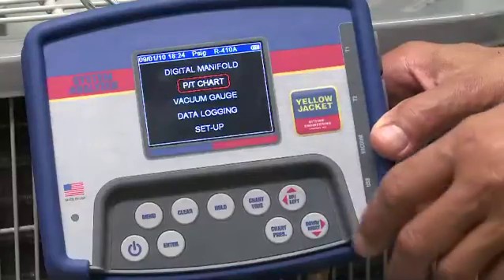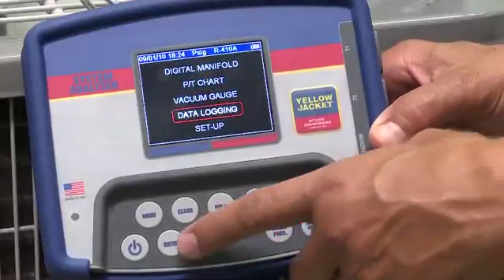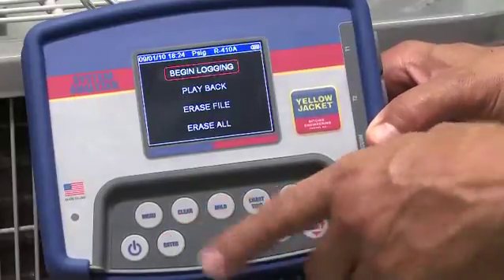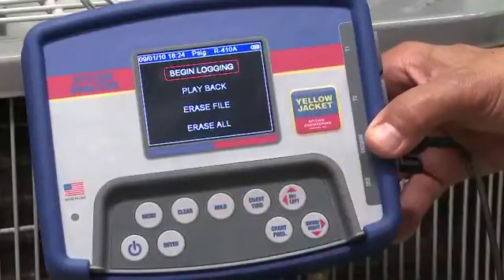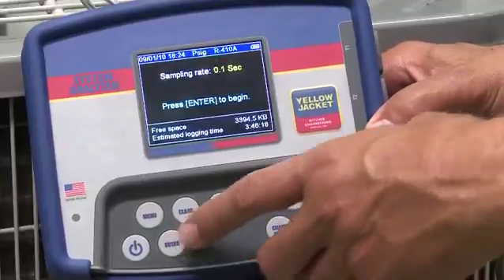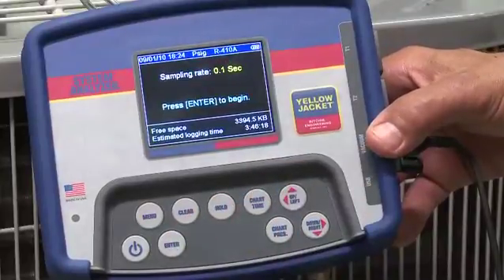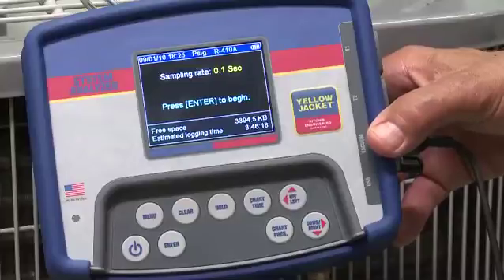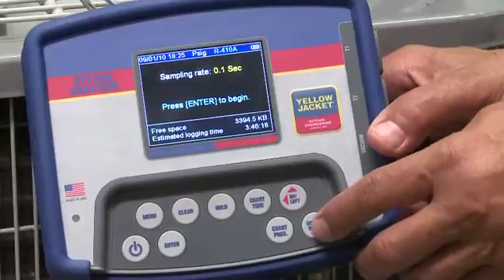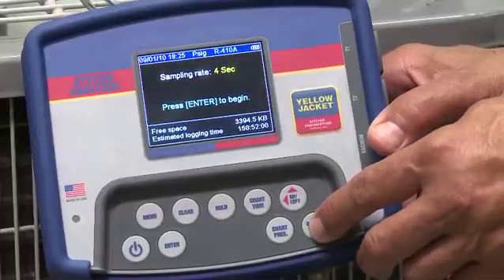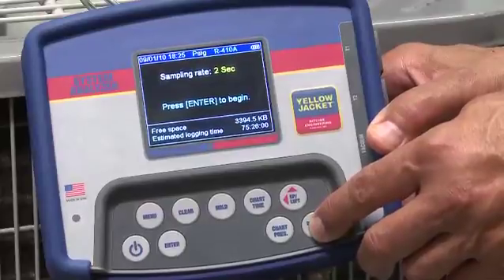Let's walk through it. From the main menu, move to Data Logging and press Enter. Select Begin Logging. From the Startup screen, you'll be prompted to select the sampling rate, which is how often your readings will be captured. You can select from 0.1 up to 5 seconds.